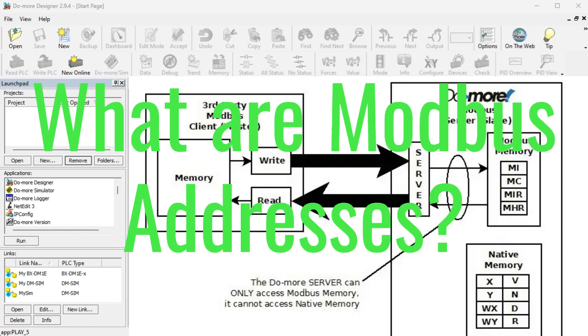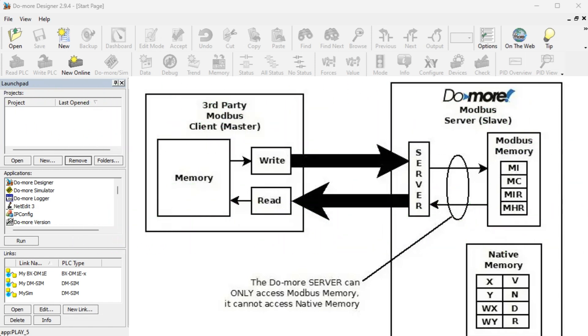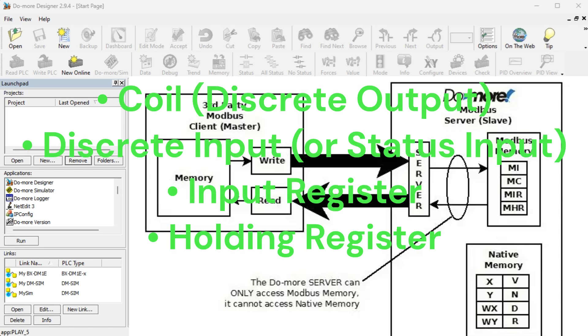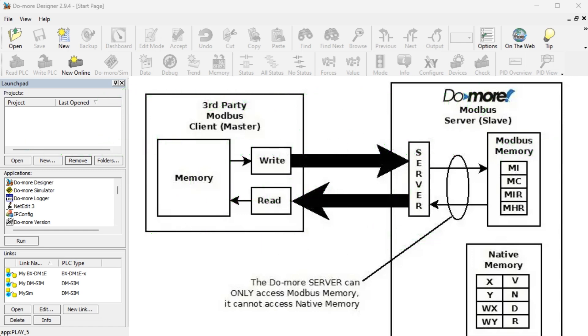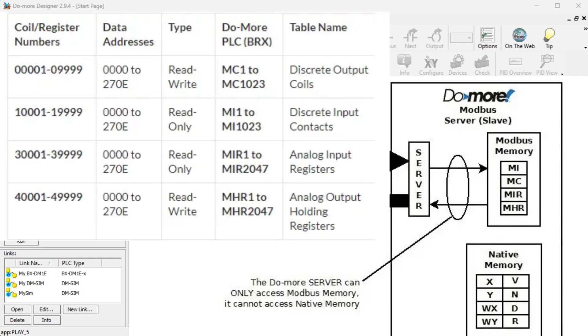What are Modbus addresses? Four types of addresses referenced in Modbus devices are: coil (discrete output), discrete input or status input, input register, and holding register. It is important to find out the Modbus addresses available at all of the slave or server units on your network. The Do More series of PLCs use a fixed dedicated Modbus memory area, as seen in the following chart.